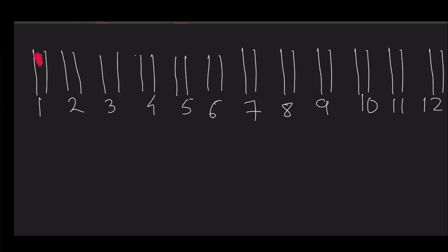Now here the upper layer again, slot per pole per phase still remains 2. We are considering the same thing, the only change between the previous example and this example is that now we are considering chording by 60 degree. So 60 degree means coil span will be 120 degree.